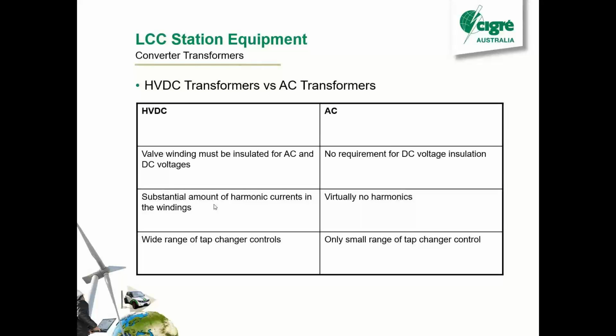And you generally need a really big tap changer on an HVDC. We can change the voltage with the firing angle, but there's certain firing angles that we like to operate at, because if we increase our firing angle too much, we start to consume a lot of reactive power, and it's not very nice. So you can account for that with a big wide tap changer range. If you went to reduce voltage, maybe you go up to 30 straight away, but then as you tap down, you could start to pull your alpha back and get back into the area where you want to operate. Yeah, so for our scheme, we've got 33 taps on our converter transformers, which is quite a lot more than you'd find on a normal AC transformer.